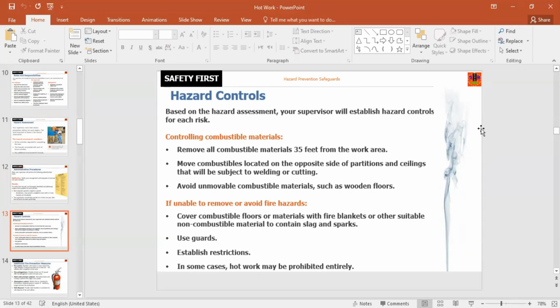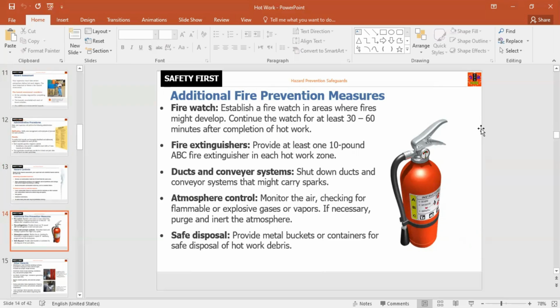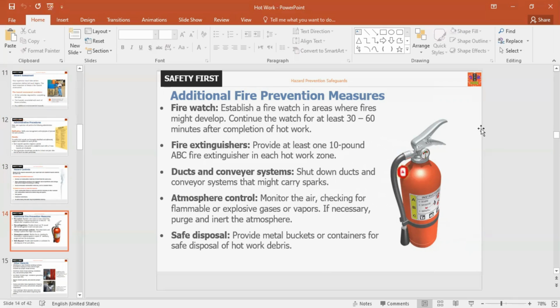Use guards. Establish restrictions. In some cases, hot work may be prohibited entirely. Additional fire prevention measures might require a fire watch. Establish a fire watch in areas where fires might develop. Continue the watch for at least 30 to 60 minutes after completion of hot work. Fire extinguishers: provide at least one 10-pound ABC fire extinguisher in each hot work zone. Ducts and conveyor system: shut down ducts and conveyor system that might carry spark.